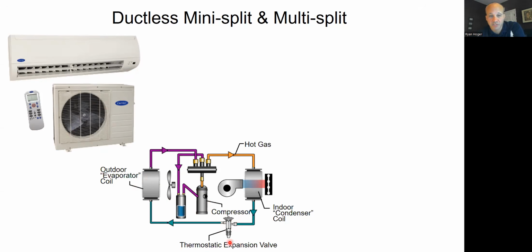The one thing about the expansion device, TXV in this case, actually two things. One, it's probably an EXV, electronic expansion valve, instead of a thermostatic expansion valve. That means a circuit board is going to drive it instead of an analog temperature probe. And then two, instead of that TXV being at the indoor unit, it's probably going to actually be at the outdoor unit.